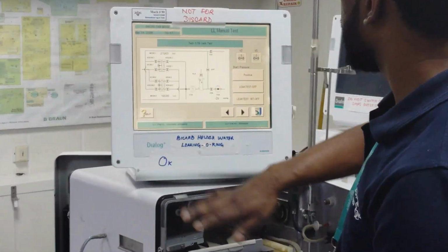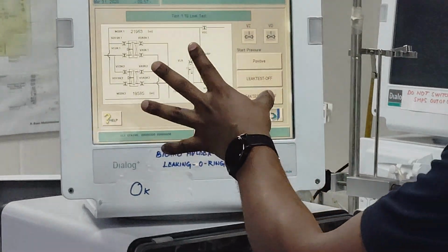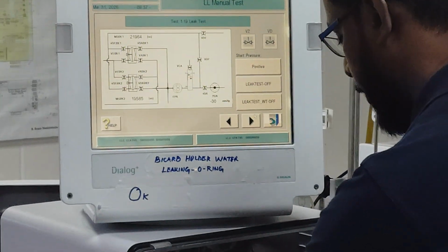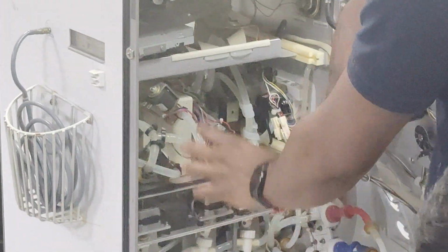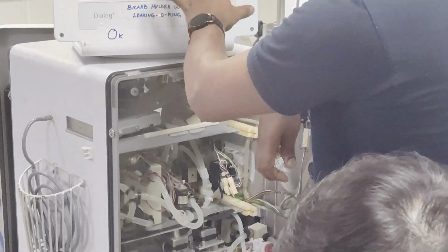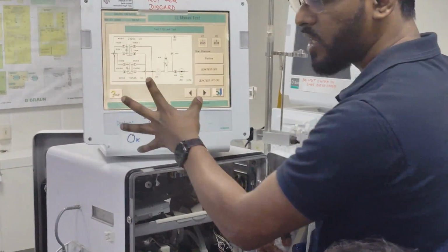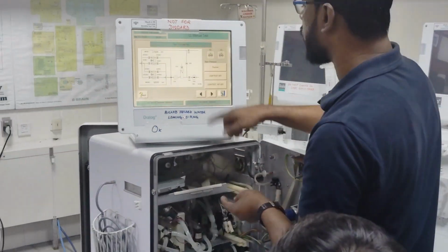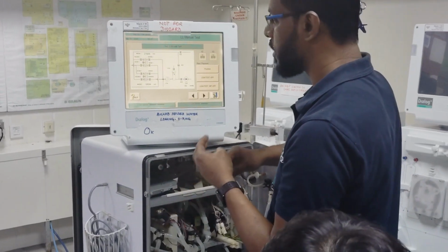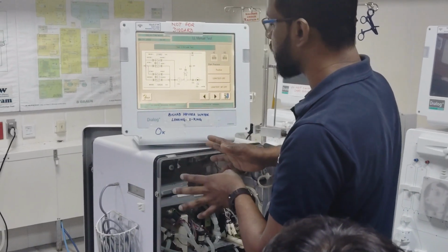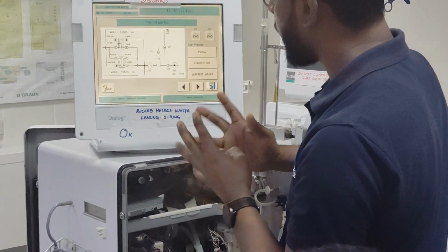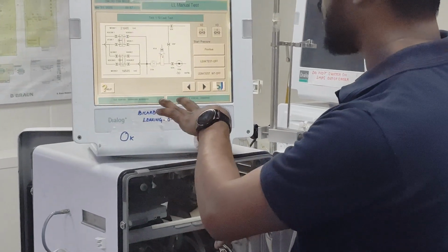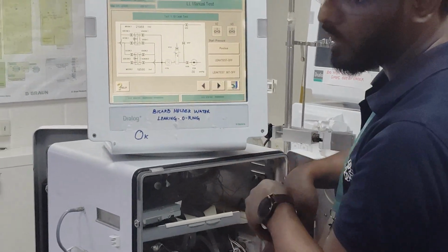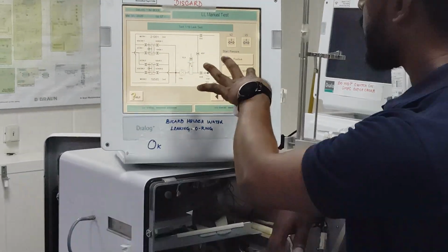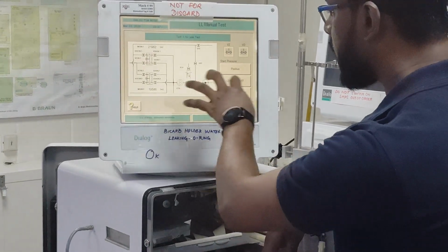And the leak test also will try to check all this inside the chamber, the valves. Most of the cases, when we run the leak test mode, it will make a test and show pass or not passing. Maybe there is leaking in some places, some valves or some membrane. So it's trying to tell us, okay, you have this point, it's trying to leak. By putting the machine in the leak test mode, we can understand what's going on.